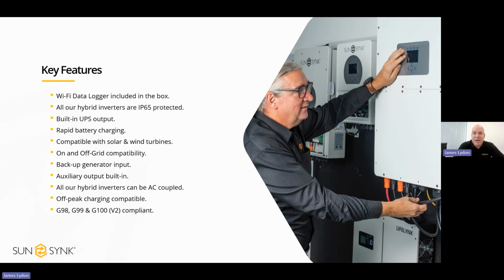All of our hybrid inverters are IP65, so they can all be installed outdoors. We have a built-in UPS output. Some manufacturers will have an EPS, an emergency power supply. Ours is a UPS, so it's completely uninterruptible. Any loads that are physically connected to the inverter will remain powered if there's a power cut.